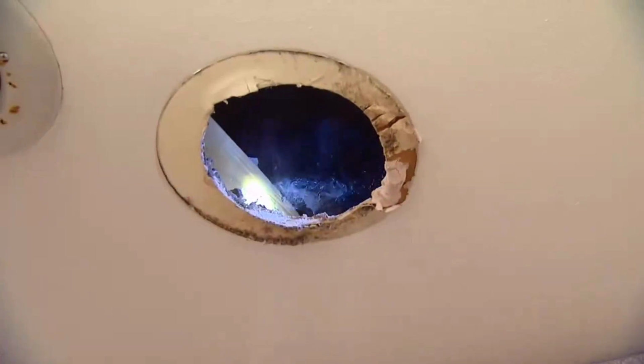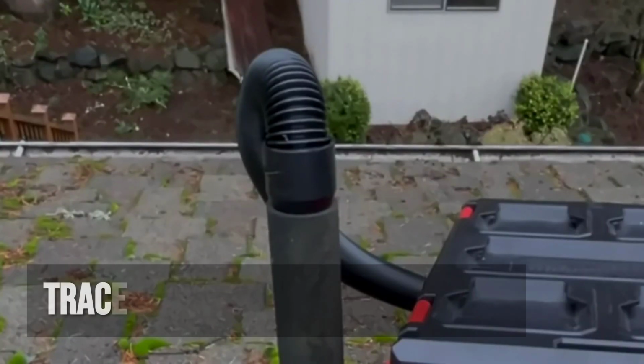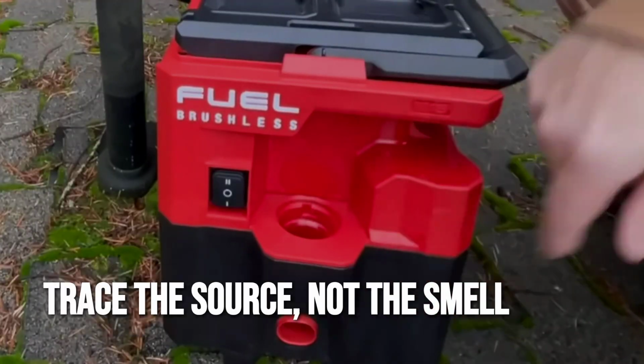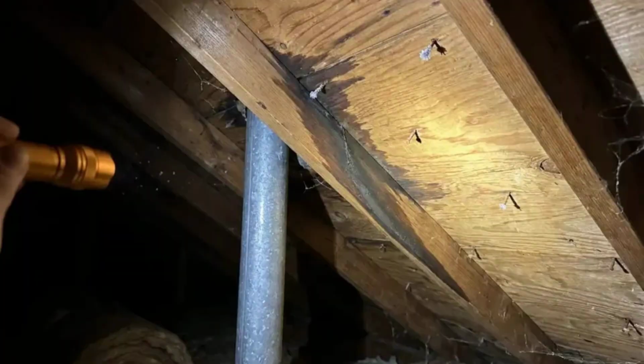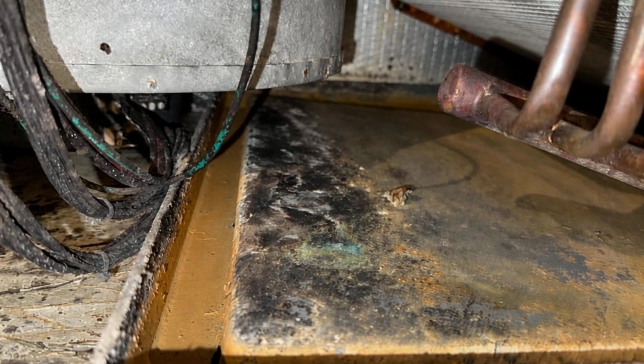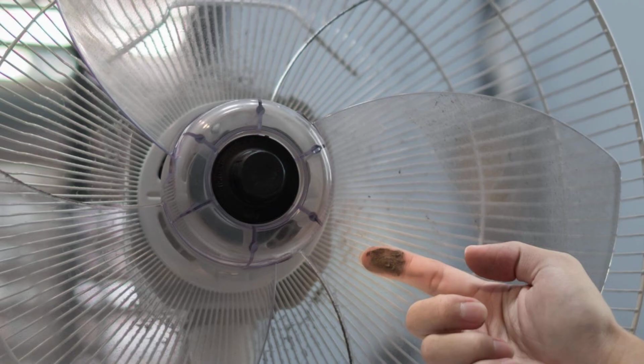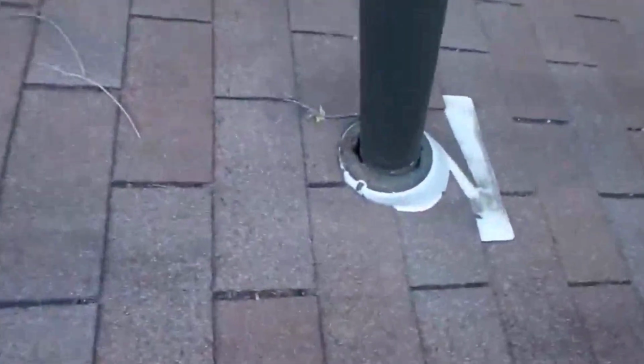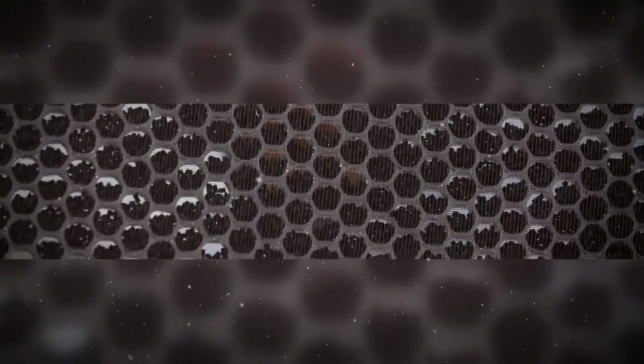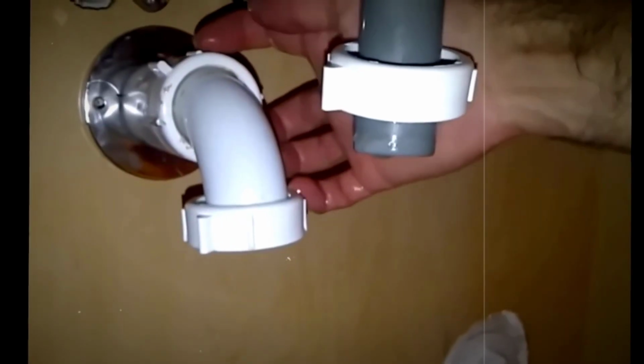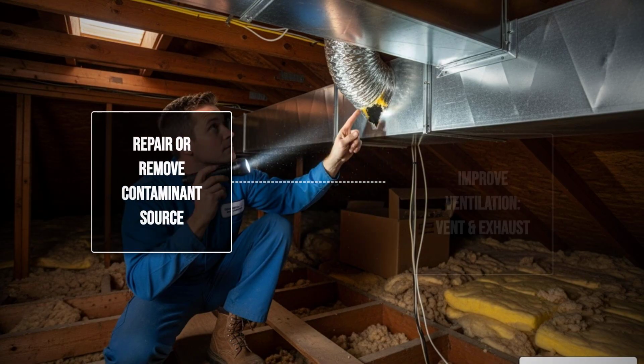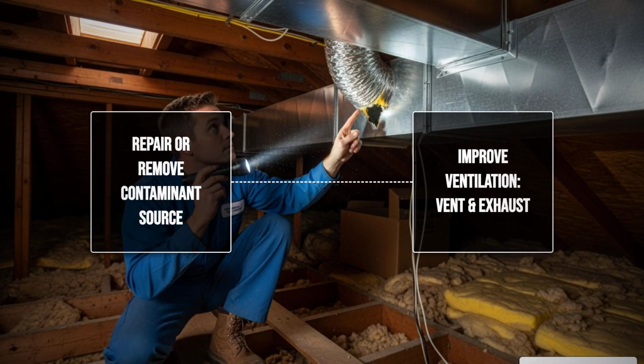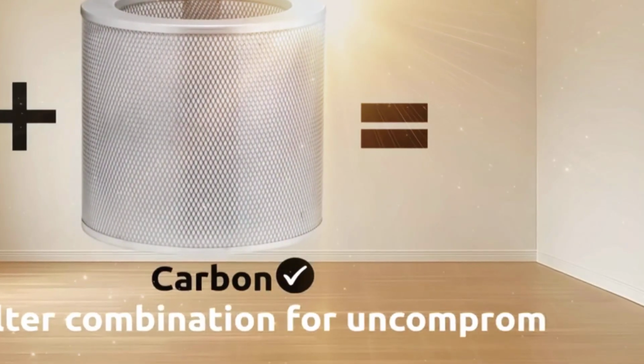The same principle applies inside a house. When you smell mustiness, sewage, chemicals, burning, or persistent dampness, do not assume the odor is the entire problem. The smell is often a warning sign. A musty odor may indicate a plumbing leak, roof leak, wet insulation, dirty drain pan, clogged condensate line, or microbial growth. A burning smell may involve an overheating motor, electrical connection, belt, heater, or accumulated dust. A sewage odor may involve a dry trap, venting problem, or damaged drain line. Activated carbon might temporarily reduce what you smell, but reducing the smell could make it easier to ignore the actual source. That is why good indoor air quality starts with source control. Remove or repair the thing producing the contaminant, then improve ventilation. Then use filtration or purification as an additional layer, not the other way around.